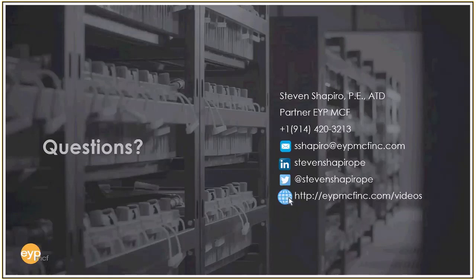Can you comment on potential design impact from NFPA 855 on lithium-ion installations in the future? So there are a lot of presentations on 855 and what it could mean until it's adopted and people follow it and people adopt the International Fire Code, the 2018 Fire Code. We don't necessarily know what's going to happen. One of the requirements is that these battery systems get UL listed at a certain capacity, and if they're UL listed, you can use them. If you looked at a megawatt of battery, or I should say a megawatt UPS with 15 minutes of battery, you're somewhere in the neighborhood of 250 kilowatt hours, and so that is the UL listed requirement associated with that battery.